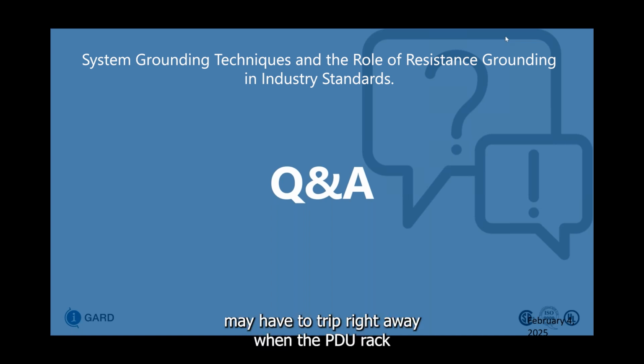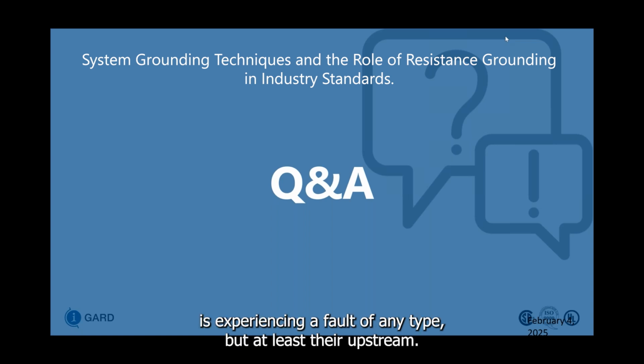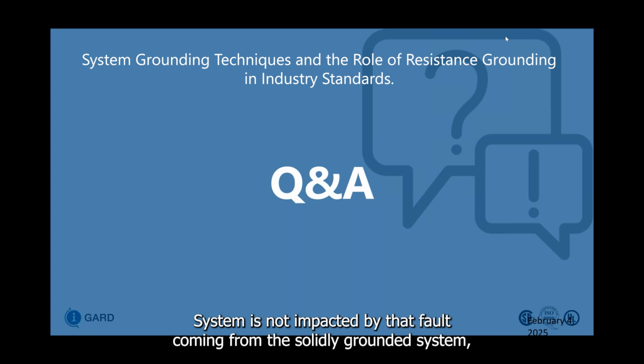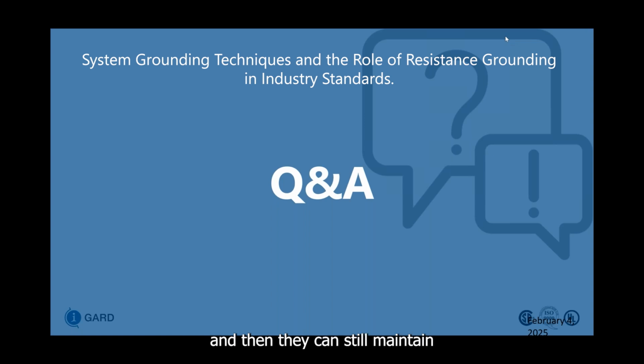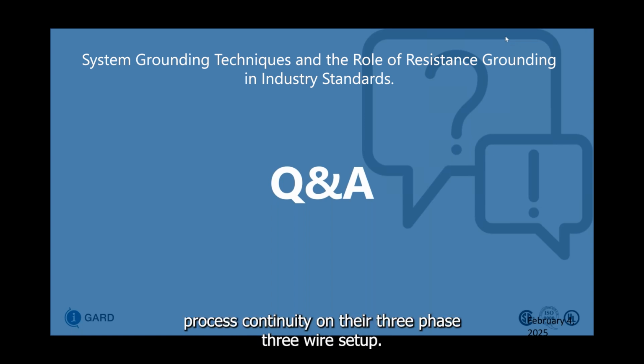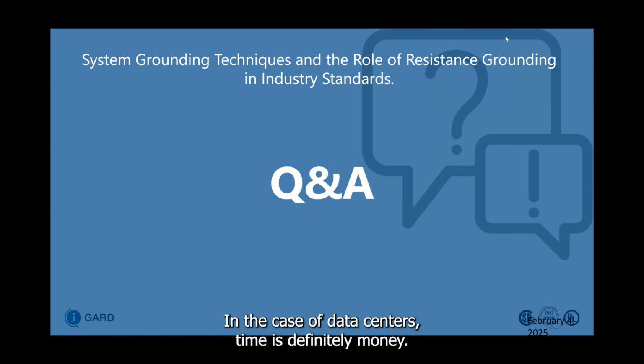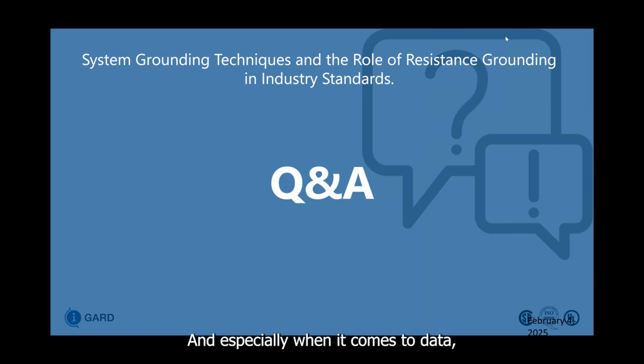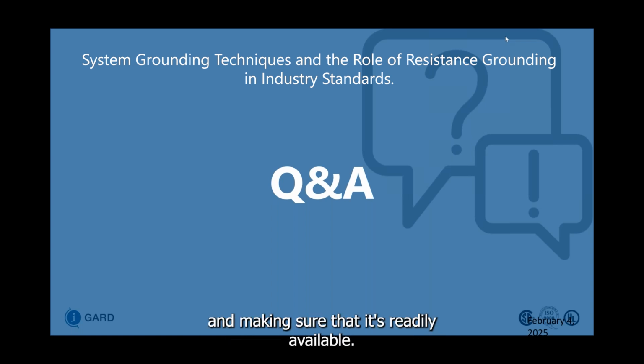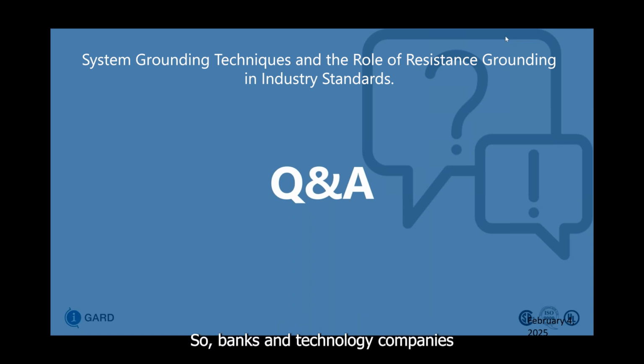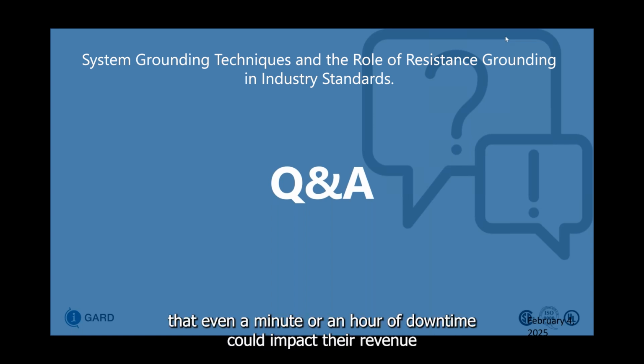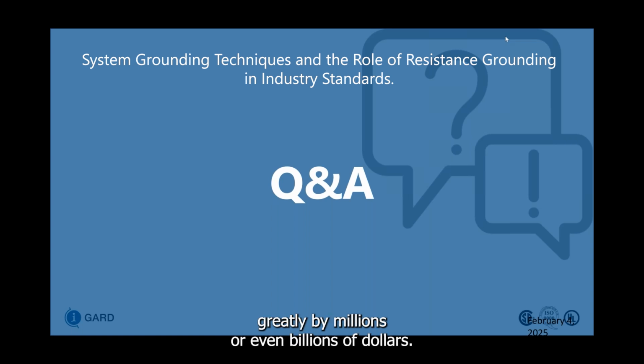Now, in that case, they may have to trip right away when the PDU rack is experiencing a fault of any type, but at least their upstream system is not impacted by that fault coming from the solidly grounded system, and then they can still maintain process continuity on their three-phase three-wire setup. In the case of data centers, time is definitely money, especially when it comes to data and making sure that it's readily available. So banks and technology companies, even a minute or an hour of downtime could impact their revenue greatly by millions or even billions of dollars.